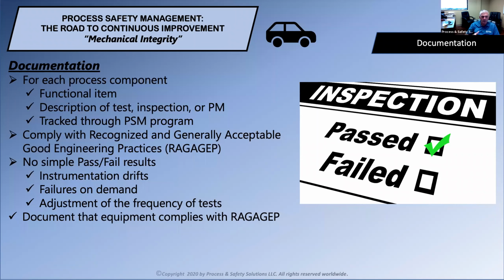Well, when we started asking questions as to what was going on, quickly we realized that the inspection that was being done on the actual instrument, in this case the pressure transducer, was not being done properly.